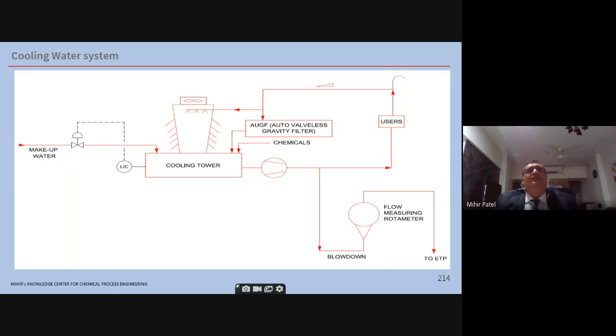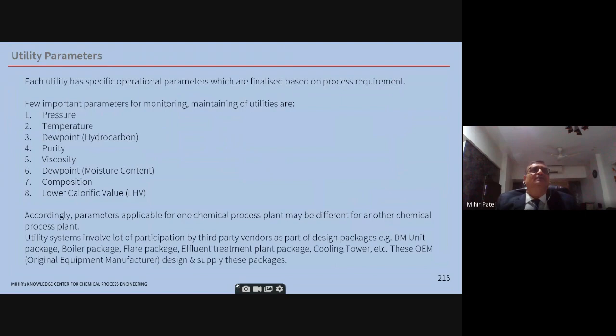So this AUGF capacity is kept roughly around 4% of the circulating cooling water. Why 4%? If you multiply 4% by 24 hours a day, you get 96%. What this means is that the entire circulation is passed through the AUGF roughly once per day. So you are assured that the entire circulation has been cleaned once per day, basically. Now there are other things in the cooling tower that I'm going to take up in the advanced course, which I will not be elaborating now.